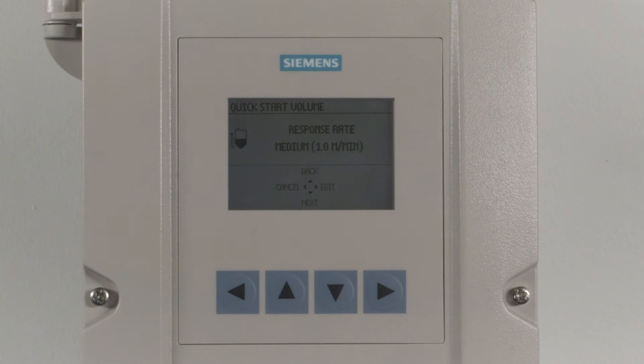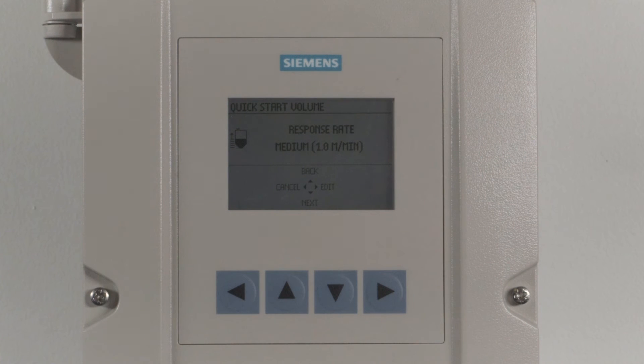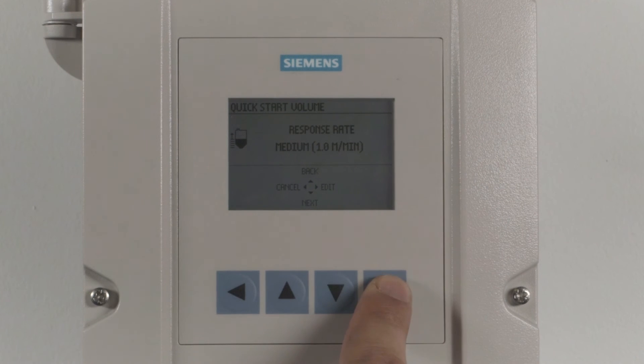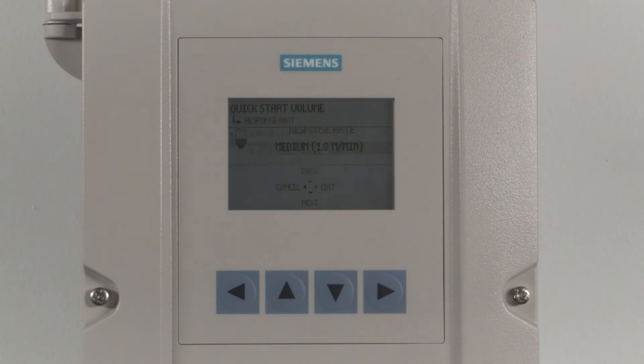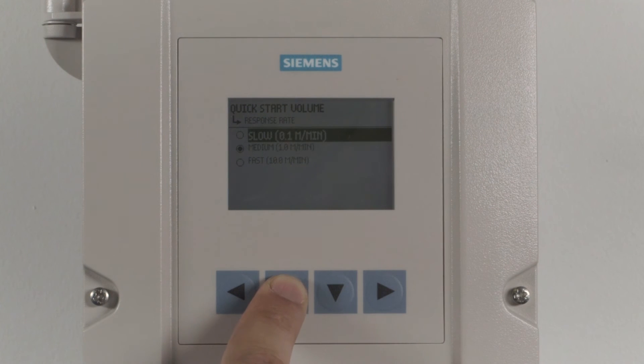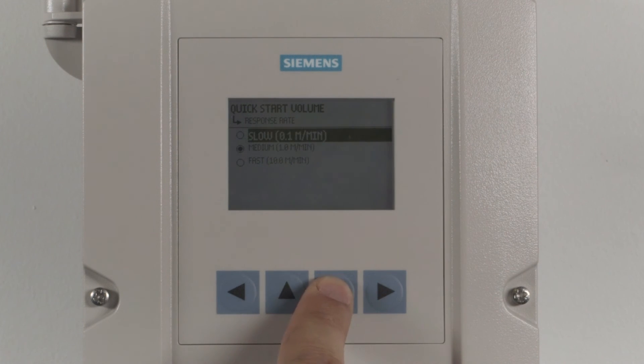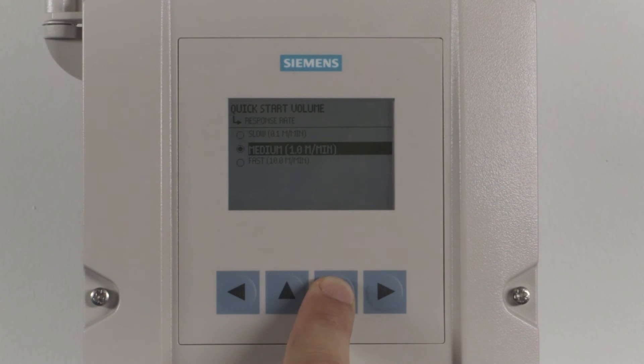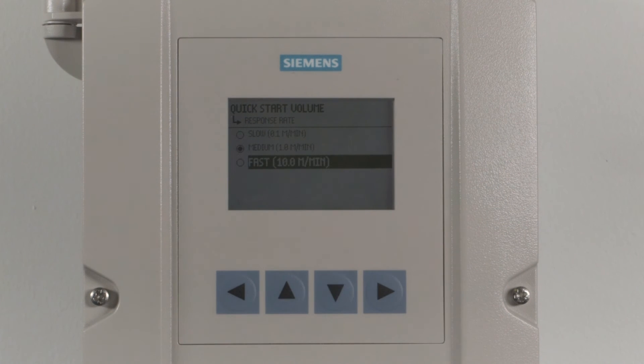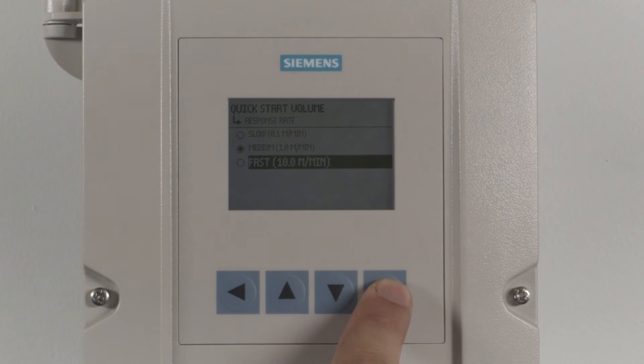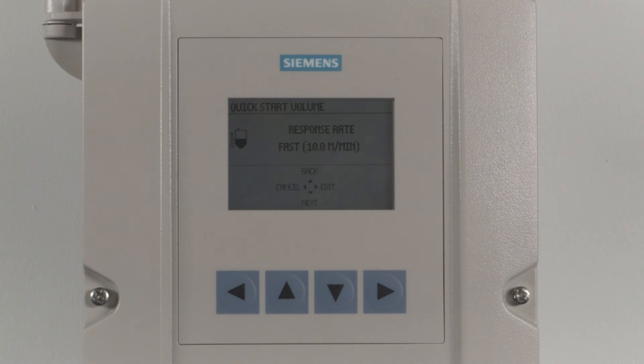The next step is to set the reaction speed of the device. The factory response rate default is set to medium, which is a rate of level change less than 1 meter per minute. Press the right arrow to modify this value. There are three options: slow, medium, and fast. Your response rate should be set slightly higher than the maximum process response change. Using the up or down arrows, highlight your response rate and press the right arrow to enter your selection. Press the down arrow to proceed.